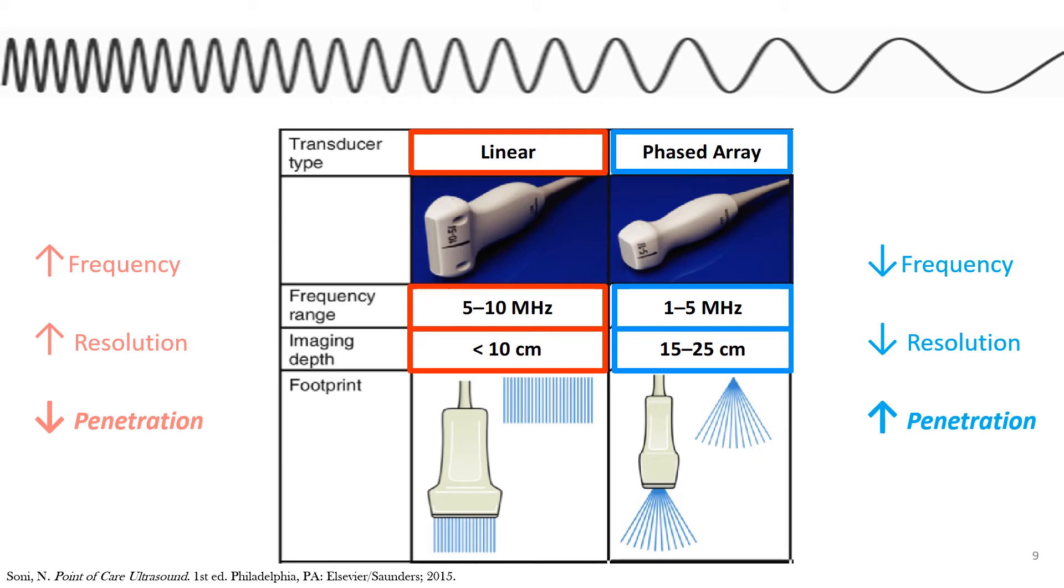The phase array probe, also known as the cardiac probe, works with low frequencies from 1 to 5 megahertz with a greater imaging depth of up to 25 centimeters and will show a triangular image on the screen.